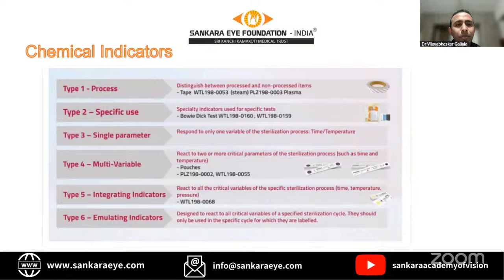Another most important thing that we use is integrating indicators, which we keep inside the set. They react to all critical variables of the sterilization process, like time, temperature, and pressure. If everything is done perfectly, only then will there be a change in the color of this indicator.